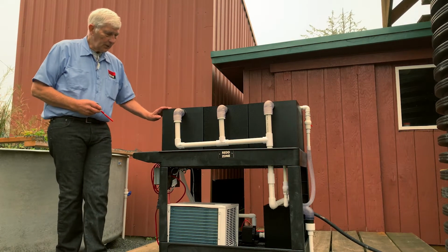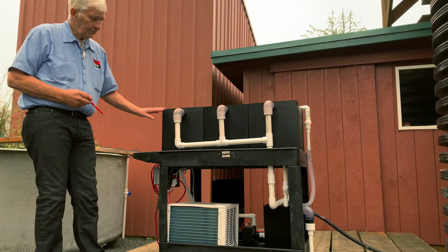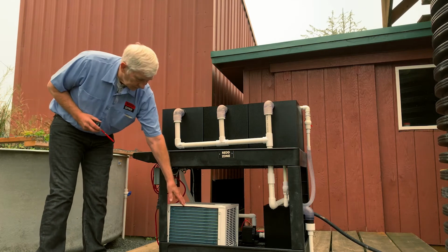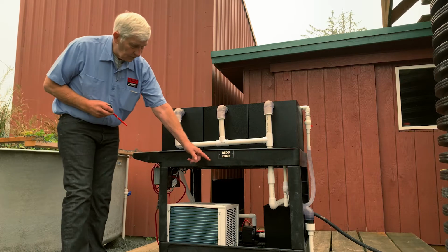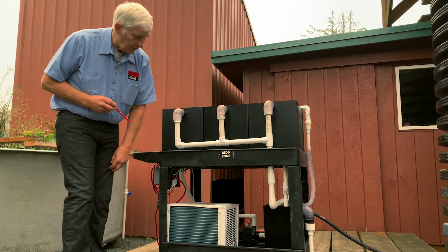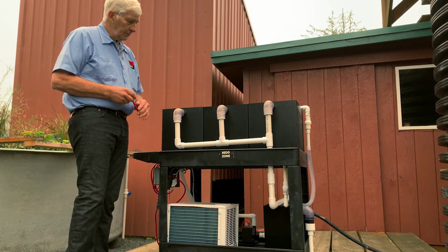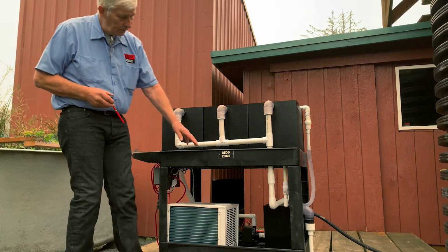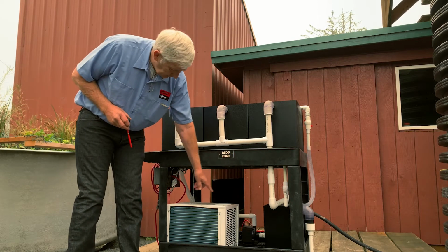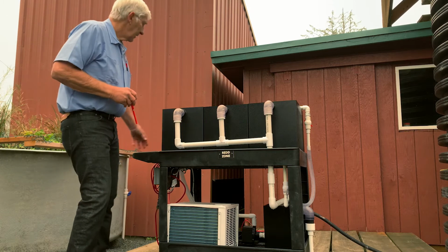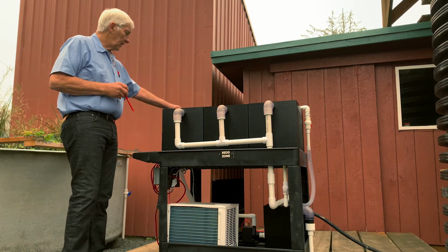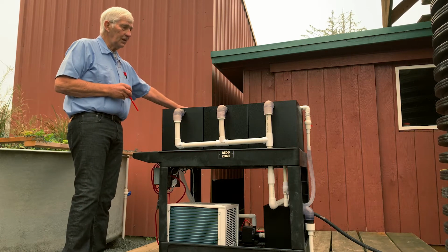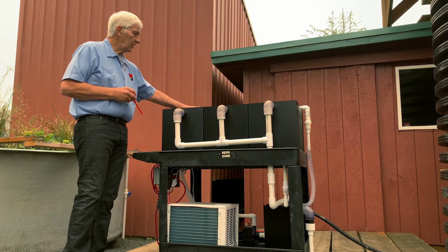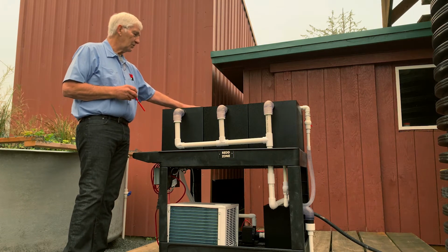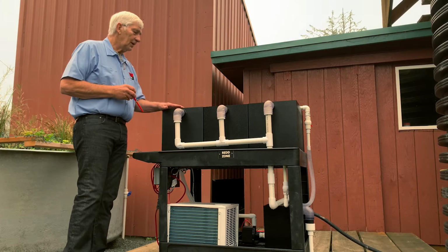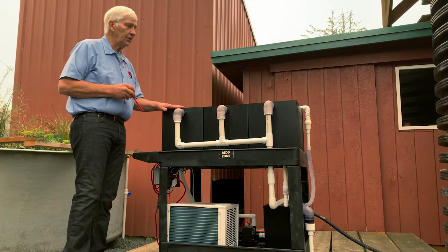There are several components to it. First, underneath we have the chiller, and over on that side is a reservoir. The flow pattern of the water is to be pumped from the reservoir through the chiller and up through the plumbing to the back of the 3 incubators. Each of the incubators is supplied with a 1/2-inch supply line, and they're running about 5 gallons a minute through each one.